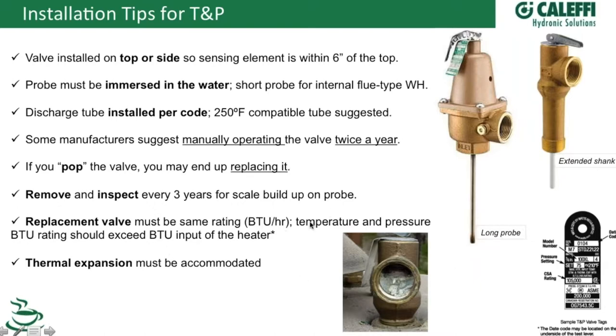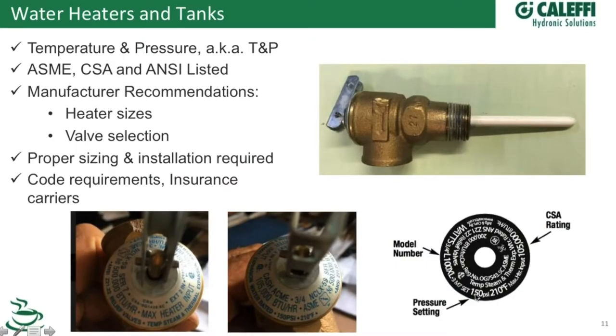One manufacturer also suggests every three years you take this valve completely out of the tank and inspect it, because buildup can accumulate on the temperature probe and then it can't sense temperature properly. You could have a valve that won't discharge when the temperature gets up to the rating — usually 210°F on the temperature rating. I've also seen probes that when you pull them out are actually starting to disintegrate, maybe from aggressive chemicals in the water. The requirement of the valve is rated for both pressure and temperature. The pressure rating on these valves used to be 125 PSI; the standard used to say 45% of what the vessel was tested for, and most residential water heater vessels are tested at 300 PSI. They've changed that recently — now they're saying 50%, so a 150-pound relief valve is what they're recommending for that vessel now.